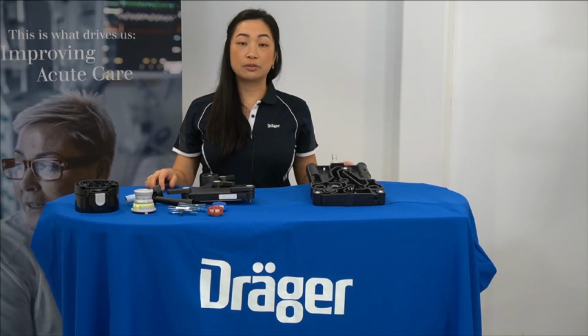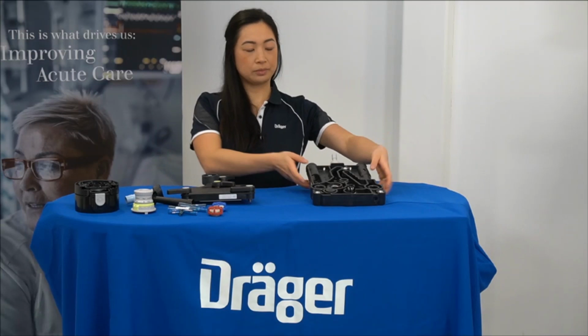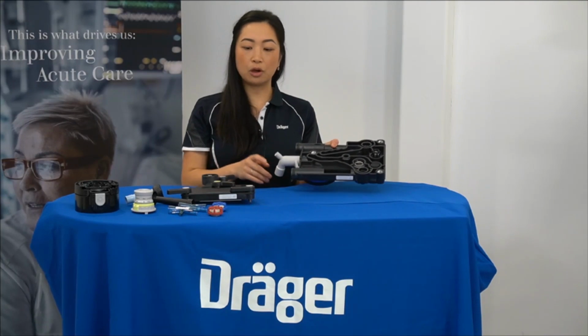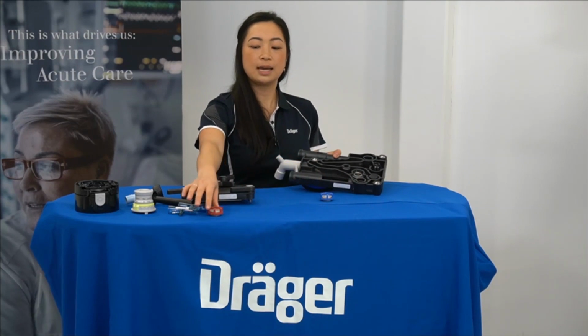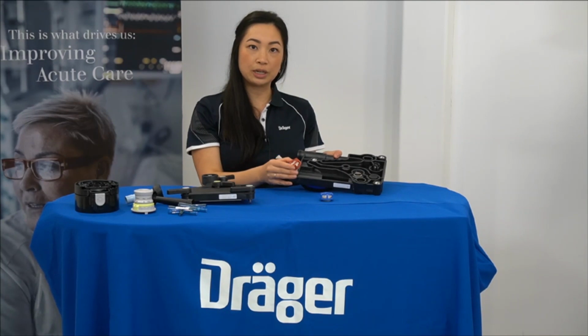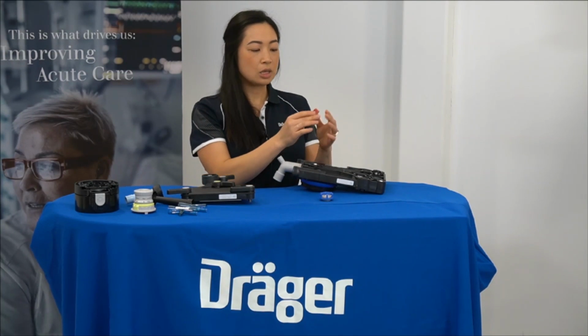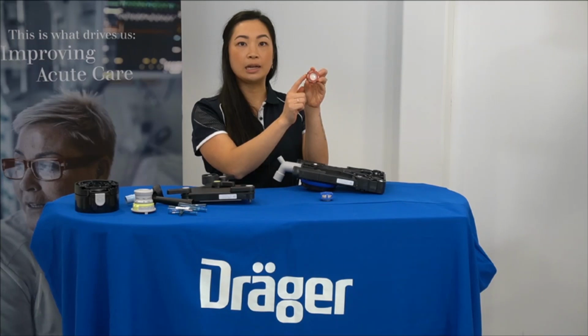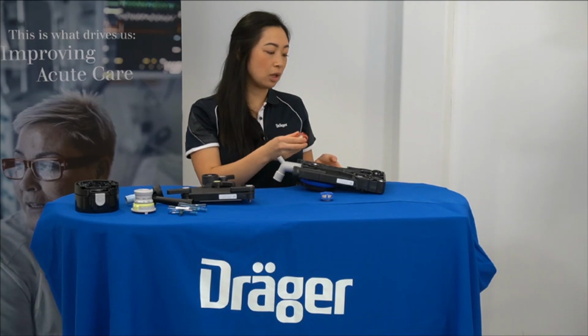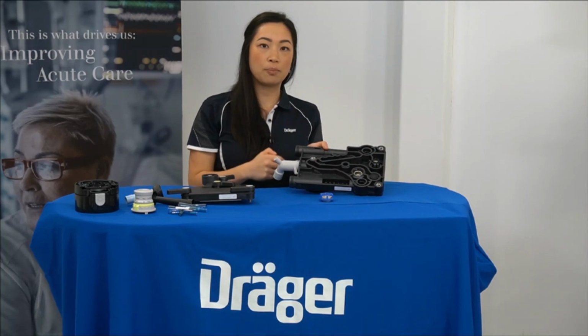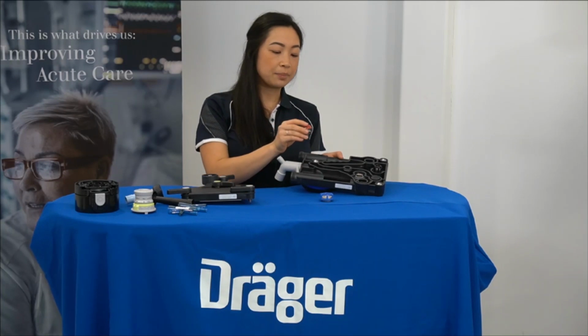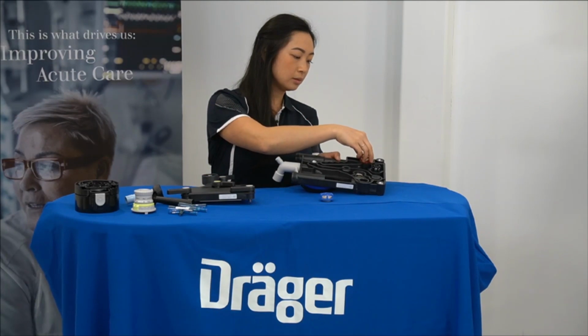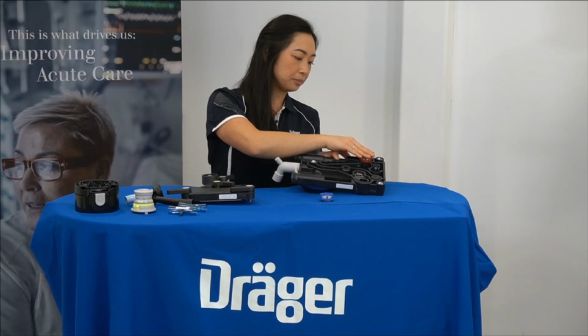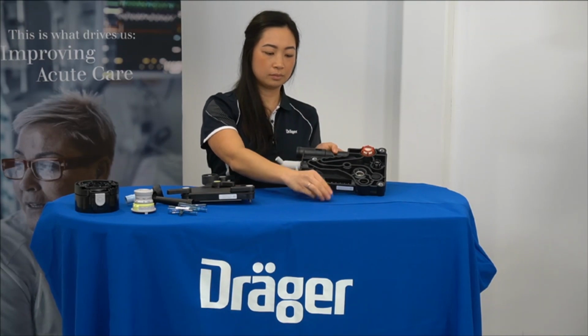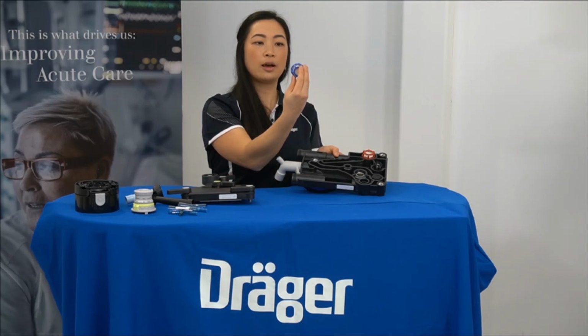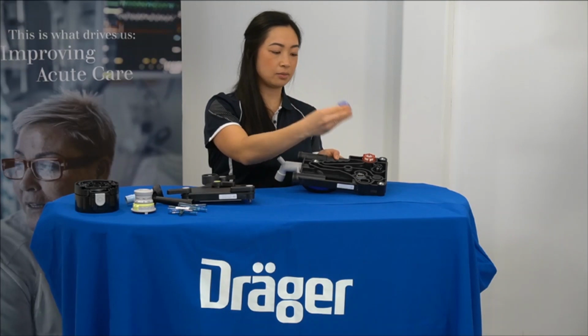Now, to reassemble the breathing block. Start with the base of the breathing block, and we'll start with reattaching the inspiratory and expiratory valves. You will be able to see notches located on the outside of the valves, which will line up with the notches on the base of the block. Simply line those up and push down. On the blue valve, the notches are at 12 and 6 roughly.